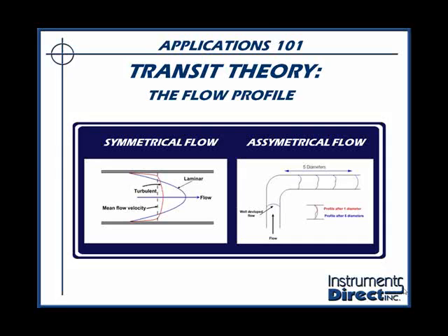In addition to the theory of operation, where does a transit time flow meter work? Well, step one, it does need to have some straight run of pipe, traditionally about 10 pipe diameters, because you need a symmetrical flow profile inside the pipe for optimum performance. The diagram on the left-hand side is a cutaway of a pipe. Again, say a man in a motorboat this time is at the center of the pipe, where the flow is indicated there and the wake is cast out towards the side. Well, this elliptical shape does change based upon the flow rates. However, it is symmetrical in that if you were to cut a center line down this pipe, the top half of flow would equal the bottom half of the flow.